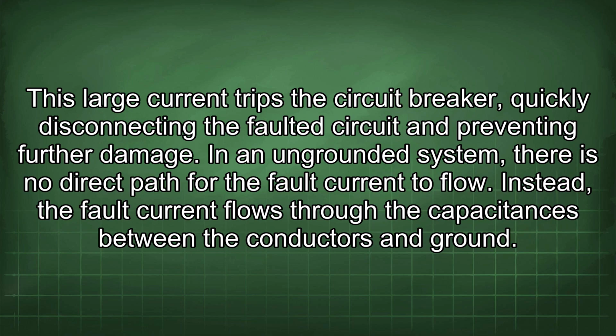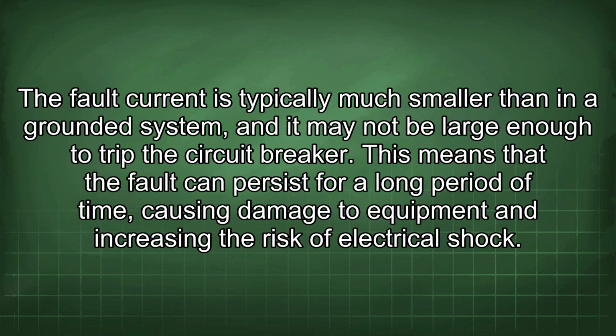In an ungrounded system, there is no direct path for the fault current to flow. Instead, the fault current flows through the capacitances between the conductors and ground. The fault current is typically much smaller than in a grounded system, and it may not be large enough to trip the circuit breaker. This means that the fault can persist for a long period of time, causing damage to equipment and increasing the risk of electrical shock.